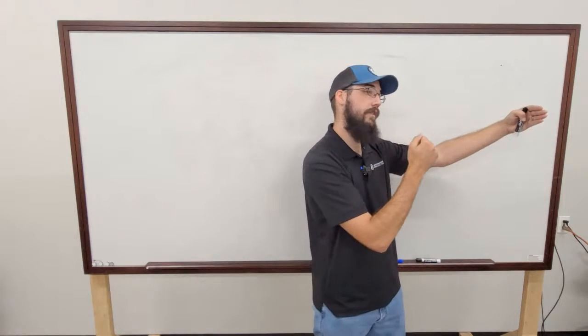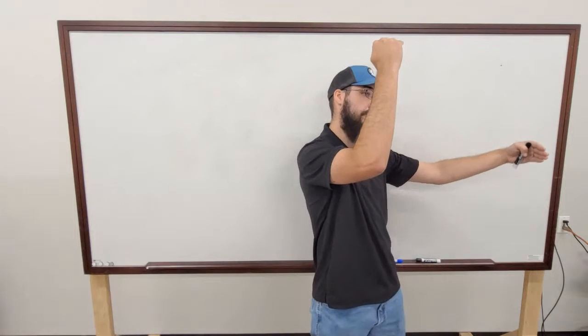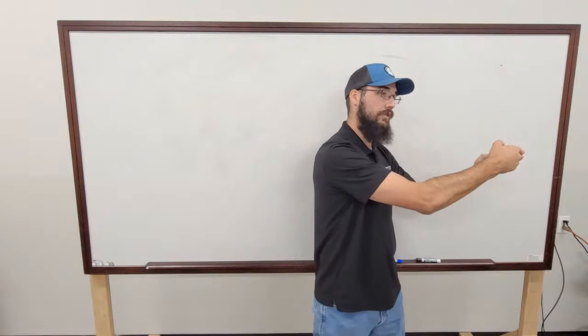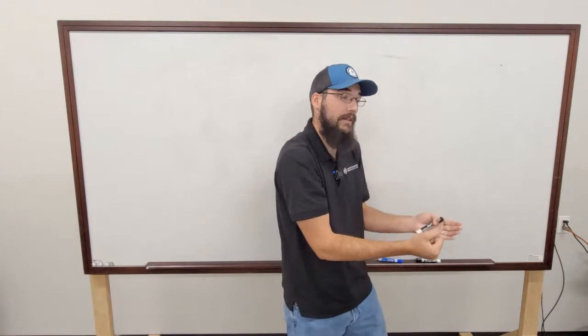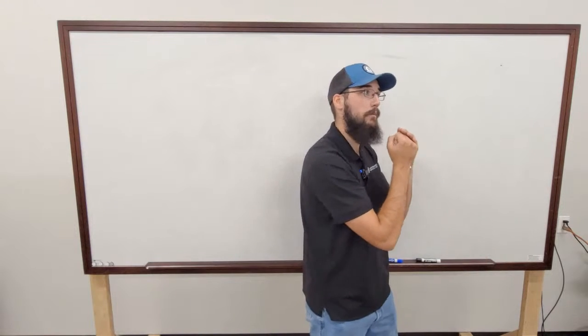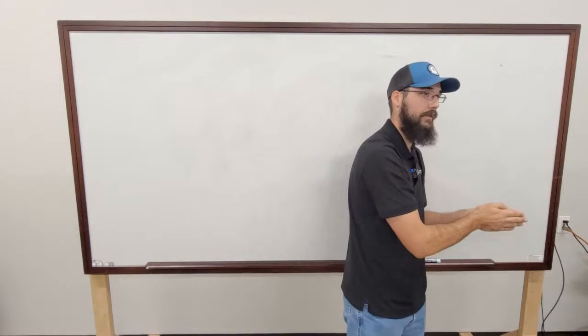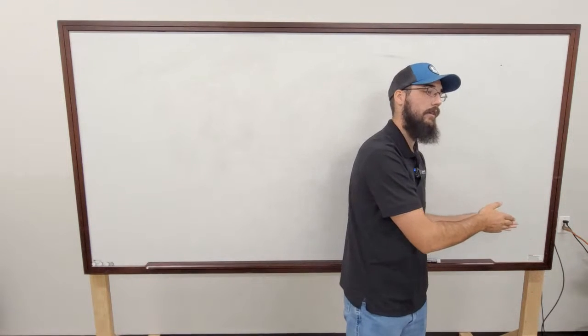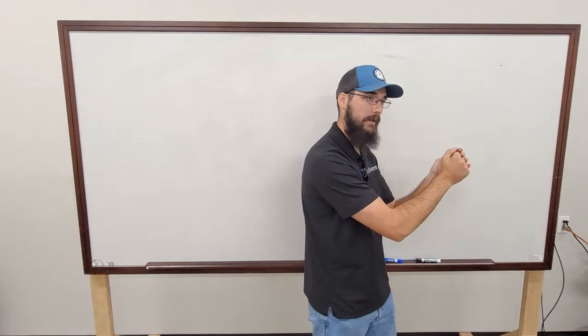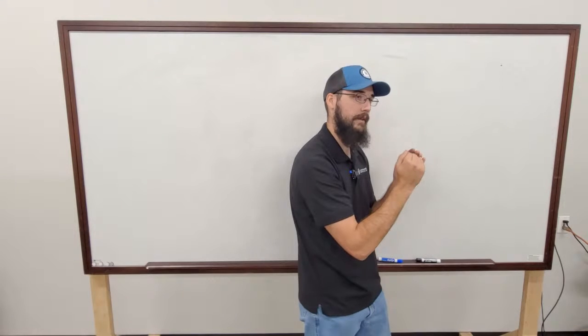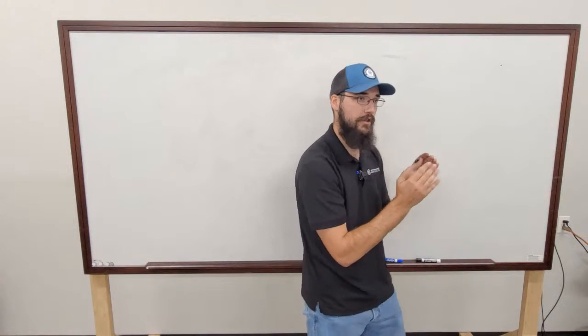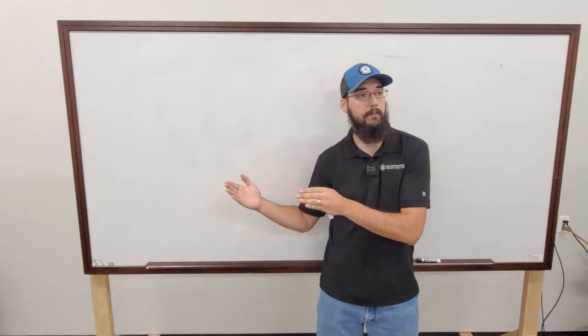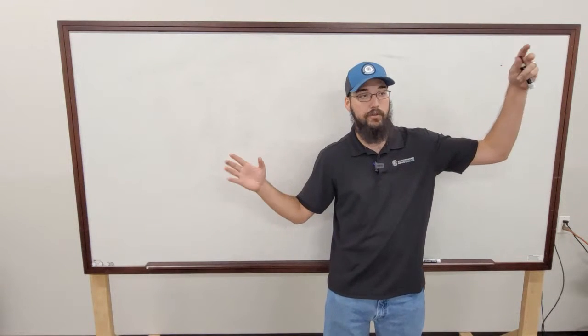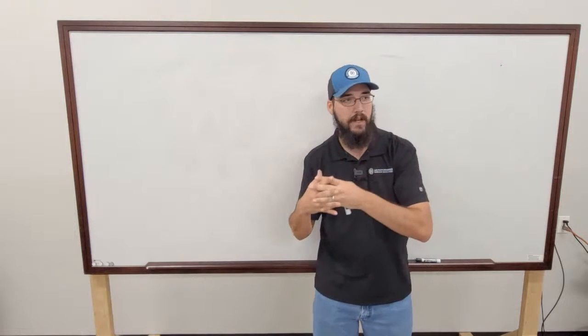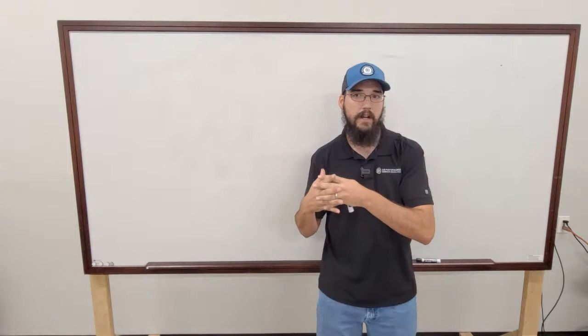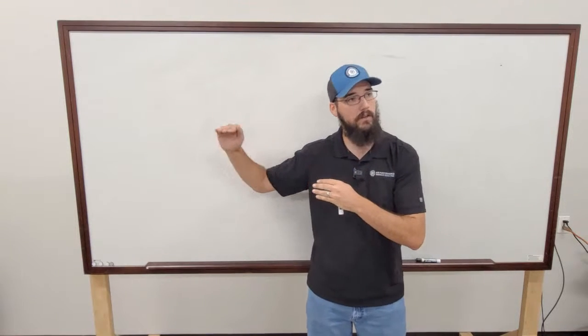So by the time you hit 75% and you're at that upper head pressure limit, the control system limits loading so that at least it can run, and it's not going to push itself into a fault on purpose, because it's bad for everybody, and it knows that. So it's going to stop short of your current limit because the head pressure limit caught it first. Just like on the low side, that low pressure limit may catch it before the current limit does. So you've got multiple safeties that are working simultaneously to try to keep this machine online as smooth and long as possible.